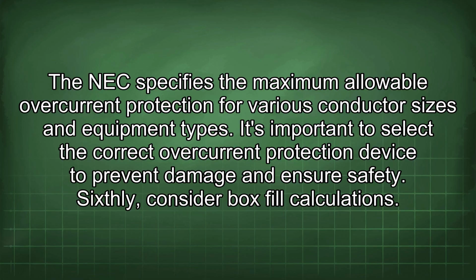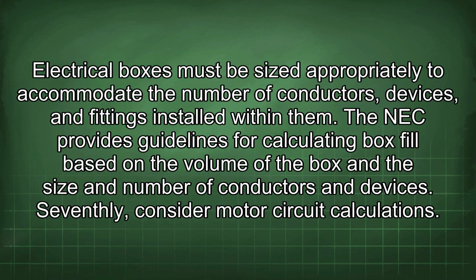Sixthly, consider box fill calculations. Electrical boxes must be sized appropriately to accommodate the number of conductors, devices, and fittings installed within them. The NEC provides guidelines for calculating box fill based on the volume of the box, then the size and number of conductors and devices. Seventhly, consider motor circuit calculations.